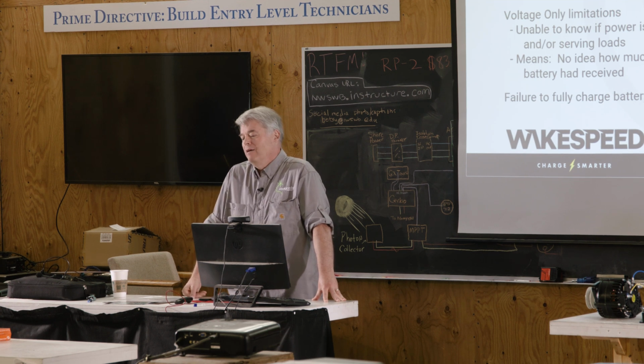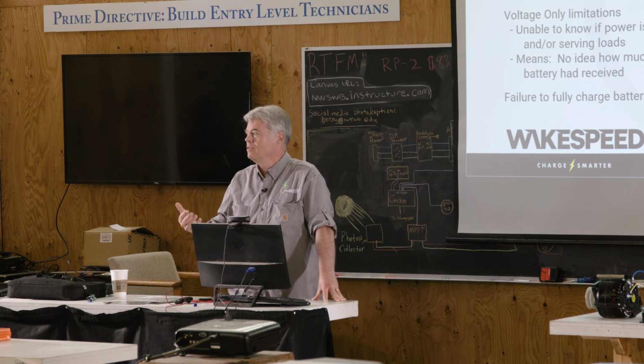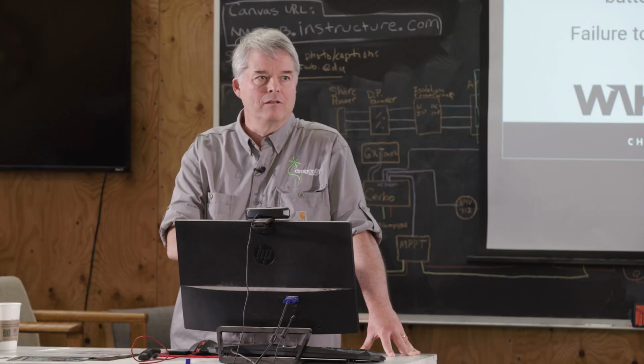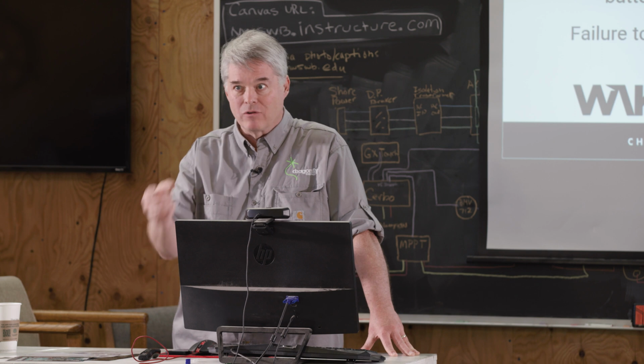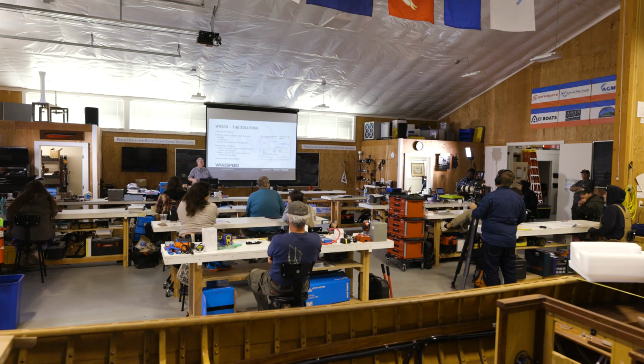So it was really a very simple problem. All you got to do is listen to the battery. And that is the first and fundamental change that the Wakespeed technology offers. We fully instrument the battery and we listen to it. We let the battery tell us what to do. We don't tell the battery what it should get. So let's go ahead and take our break.